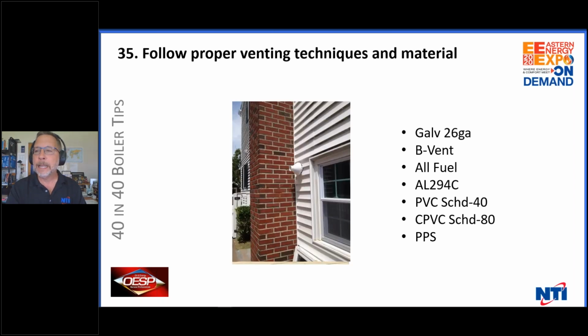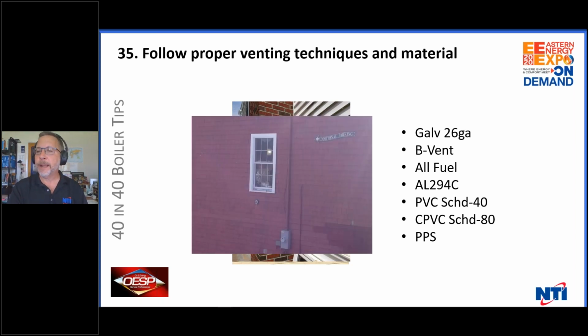Isn't that amazing? Oh yeah, venting with a concentric vent right next to a flue. Constant cross-contamination with this one, bringing the products of combustion that are going out back into the intake, and because they can't get away from there because the chimney or a wall's next to it, they're just recirculating back into the boiler. Yeah, this is great, huh?